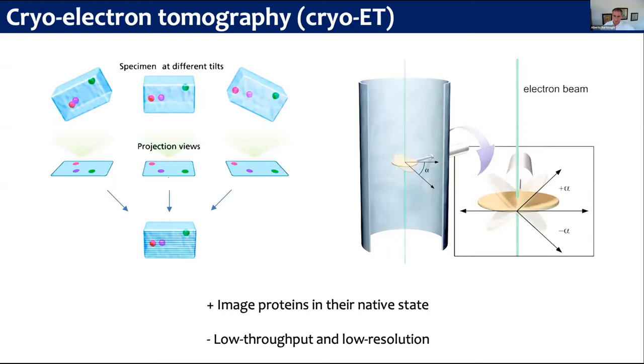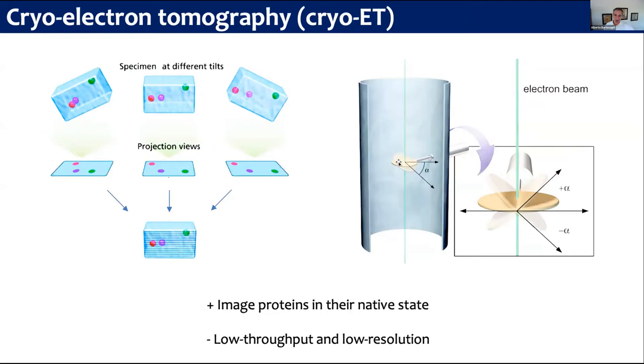The main difference in cryo-electron tomography compared to single particle cryo-EM is how we're taking multiple images of each area of our sample. The way we do that is we tilt the specimen into different orientations. For each of those orientations, we take a projection image, and then using computational techniques, we can combine those 2D projection images from the same object into a 3D reconstruction, which we usually call a tomogram that represents the 3D density of the sample. The tilting happens in the microscope by mechanically tilting the stage. At each angle, we take all these projections and then combine them together.